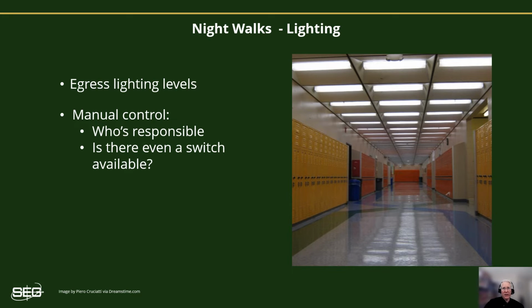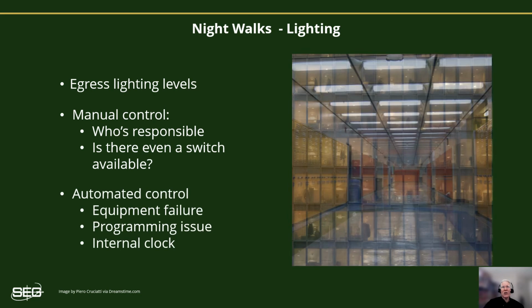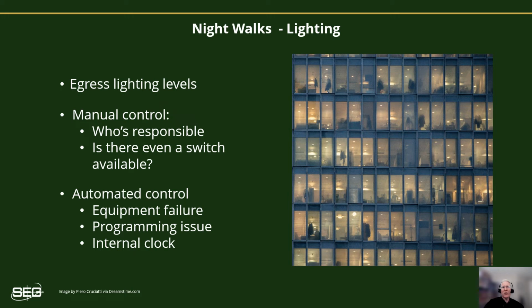If you find lights left on, look to see how they're switched. If it's manual, see who's responsible for shutting them off, and make sure they know where the switches are located and that they know that they're responsible for turning them off at night. Lighting controls don't always act as expected, so unless you make a visit after hours, you may never know what's misbehaving. You may find broken equipment or controllers that need reprogramming, or something as simple as the controller clock simply needs to be set. And don't overlook exterior lighting as an opportunity to save energy.